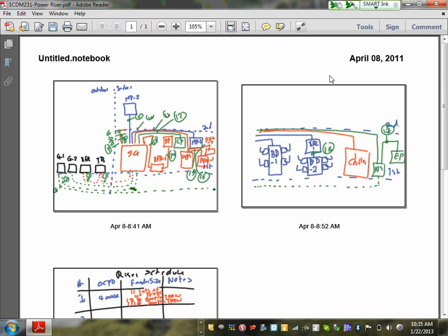And then on this transfer switch, it depends on what we're doing with these generators out here, whether we're bonding it, whether we're separately deriving the system on the generators. These will be non-separately derived systems. Okay, so there's two options. When you're doing a generator, you can either bond the neutral and the ground at the generator and treat it as a service. At that point, because it's got its own neutral and ground being derived here, this transfer switch has to be a four-pole transfer switch. In other words, you have to switch not only phases, but the neutral as well. Now, the other option is to run the grounds and the neutrals from here back to the service.